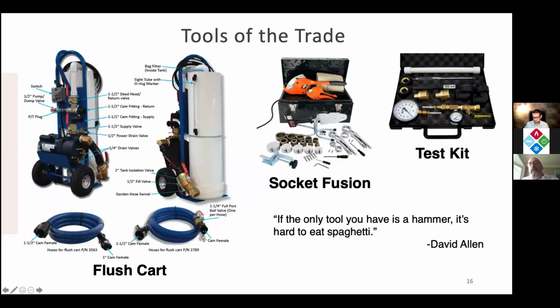They're great because you want to make sure you get all the air out of the loop. Remember, when you put the pipe in the ground, it's full of air, and now you're changing that to 100% water with ethanol, methanol, or glycol. So you want to make sure the air has been discharged. Micro bubbles sometimes happen, and at some point they can cavitate and collect, causing a nuisance service call down the road. Flushing the loop is key: let it run for a while, make sure all the air is out, pressure test it, and make sure the water level doesn't drop when deadheading it, so you know the air is out.